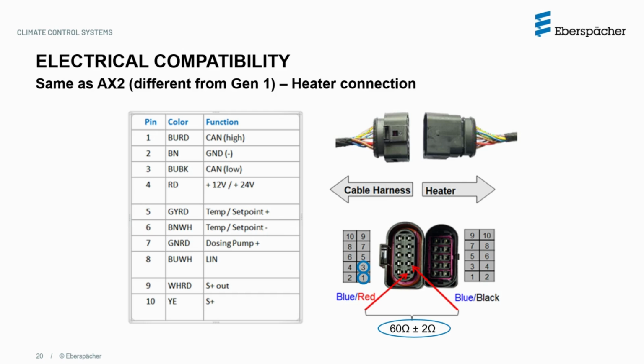You can see here the great reminder to always check the harness resistance as part of a troubleshooting procedure or at the end of an installation. You must always have 60 ohms plus or minus 2 ohms between pins 1 and 3, which are the blue-red and blue-black wires.